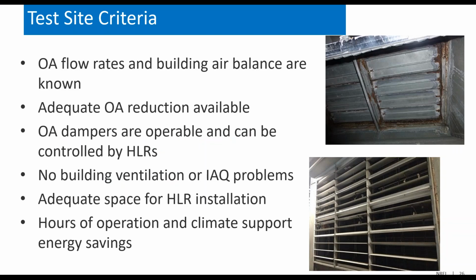So just to start out with what our test site criteria was, and this is important if you're considering adding this technology to your building. One thing is that you really need to understand what your outside air flow rates and your air balance in your building are, because you're going to be reducing the outside air by closing your outside air dampers with this technology, and that's how you get your energy savings. But you need to make sure that there's enough reduction in that outside air available to offset so that you can realize those energy savings. So obviously, the dampers need to be operable, and they need to be controlled by the HLRs or through the HLR signals.